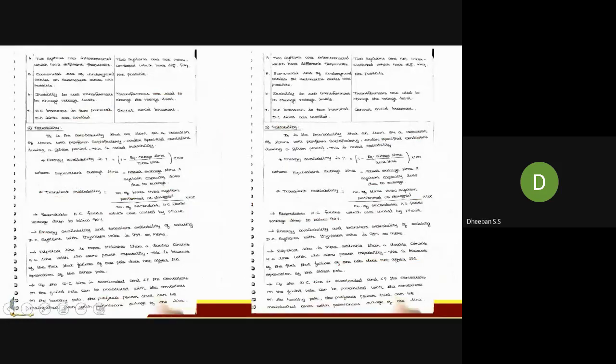Next, coming to the fourth point. Here two systems which have different frequencies can be interconnected. In the other case, the two systems are not interconnected. Economical use of underground cables is possible. As I said, up to 40 km you have to go for EHVAC; above 40 km you have to shift to HVDC.